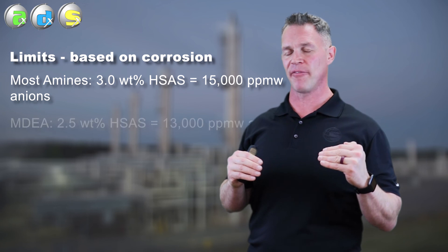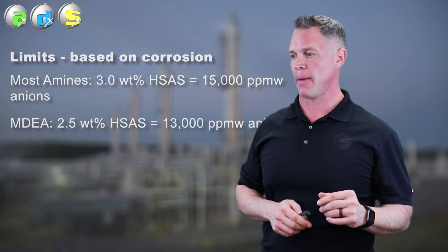In MDEA plants, MDEA is a lot more sensitive to heat stable salts than other primary and secondary amines. There we need to lower our limits a little bit to about 2.5% total heat stable amine salts or around 13,000 ppm anions.